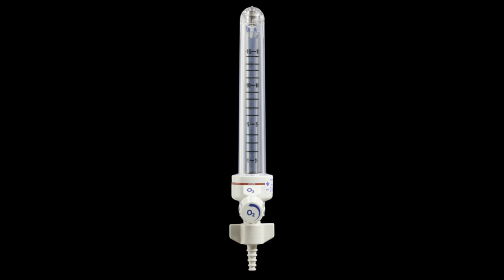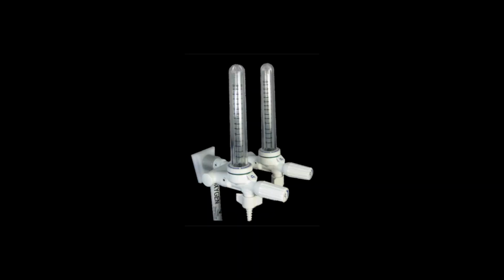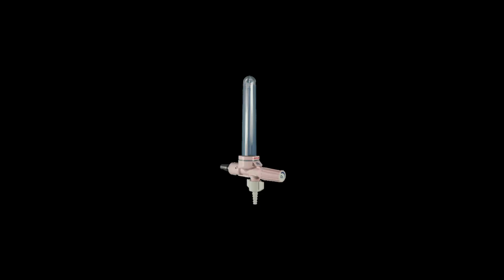Firstly, there are two different types of flow meters. The one that you will commonly see is white, and it is standard O2 flow meter, 0 to 15 litres. There is also a pale pink flow meter, and that is known as a low flow meter, and that's a 0 to 2.5 litres, only commonly seen on pediatrics.